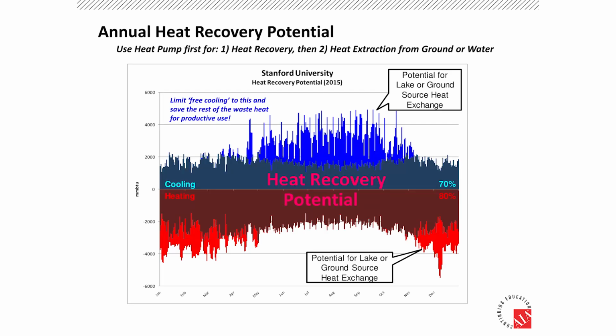If you look at it for a whole year, it looks like this. These are the months of the year on the x-axis and the energy on the y-axis, with heating below the x-axis and cooling in blue above the x-axis. You can see obviously more cooling in summer, shown in bright blue, and more heating in winter months. The overlap is shaded between the two, and it shows that at Stanford, about 80% of the heat we use each year can be made just by harvesting, with heat pumps, our own waste heat from cooling, turning it into hot water and using it.